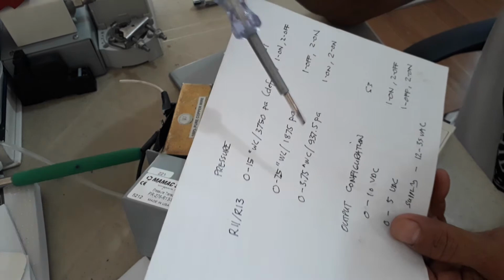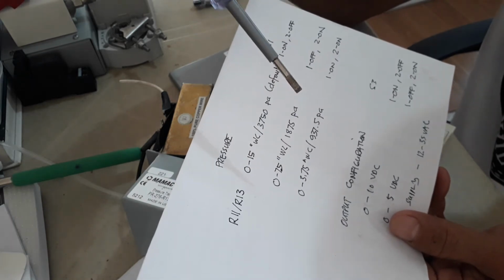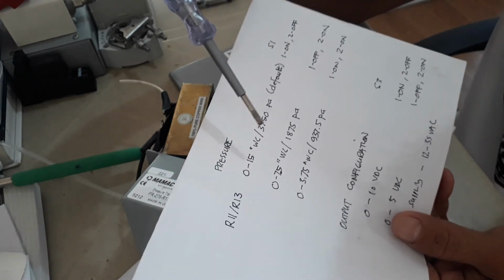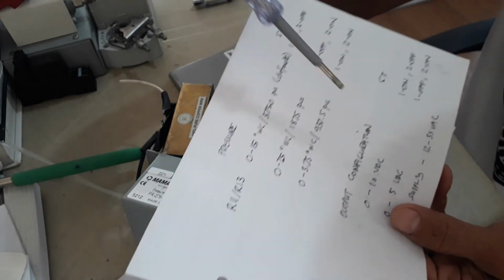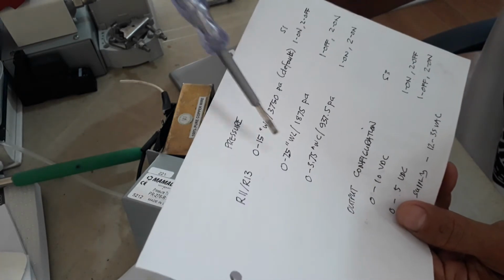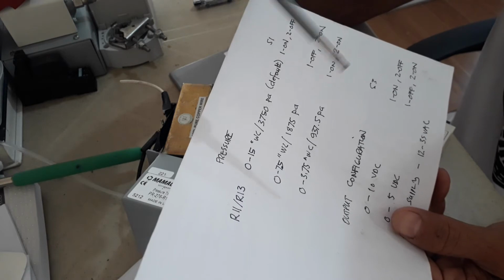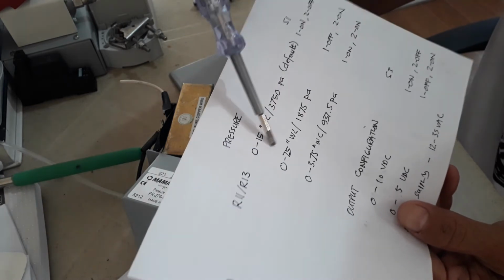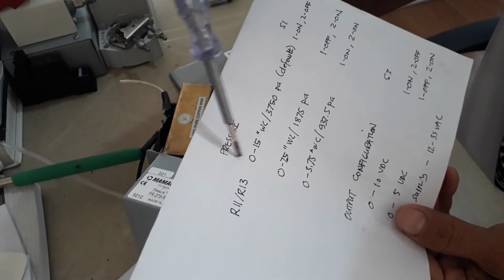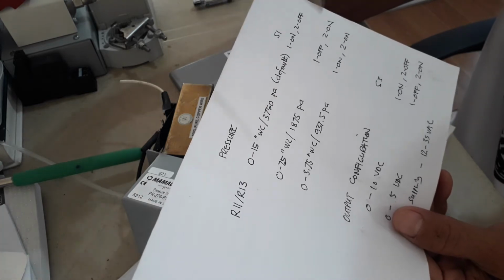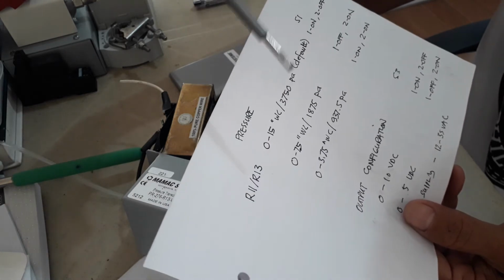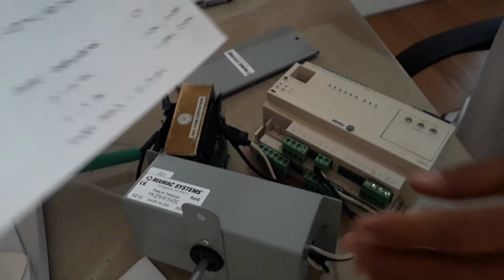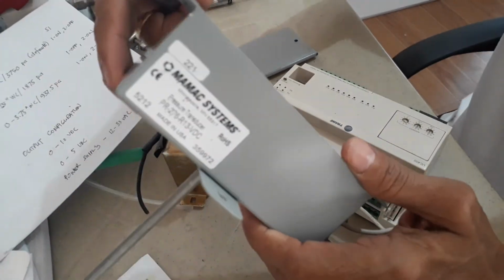Now, pressure range depends on the use of your system. You can use it in air handling unit or in staircase pressurization and some other application. Just make sure you will set the correct pressure range. Okay, so you will get an accurate reading.